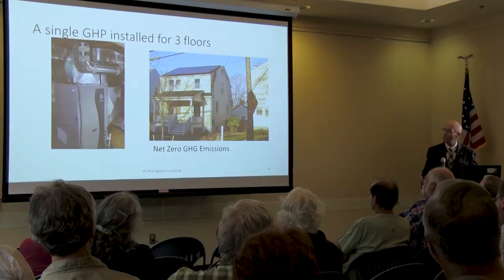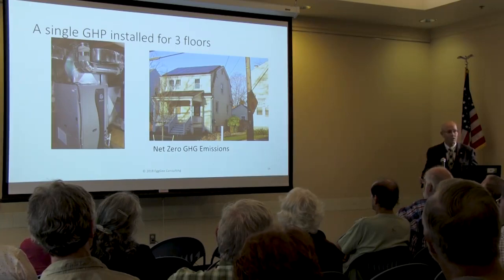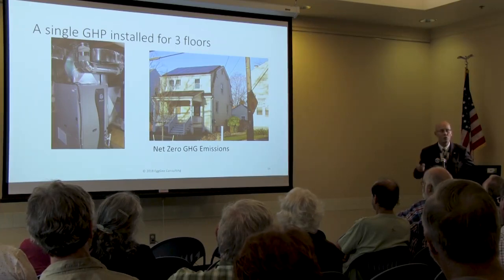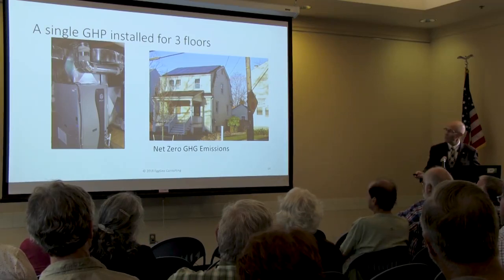And then he could, because it reduced the consumption, or the peak consumption, of his electricity. Now, the way to do a system is you want a tight building first, then you've got to eliminate greenhouse gas emissions. In other words, use an all-electric appliance such as a geothermal heat pump, and then you can add the solar generation if you want to go net zero, because it's going to be easier to do once you have reduced the energy consumption to the greatest extent possible.